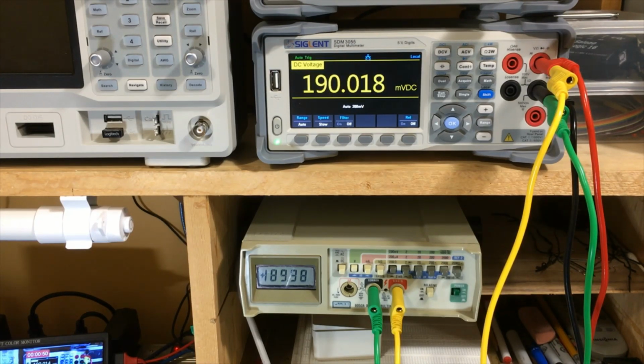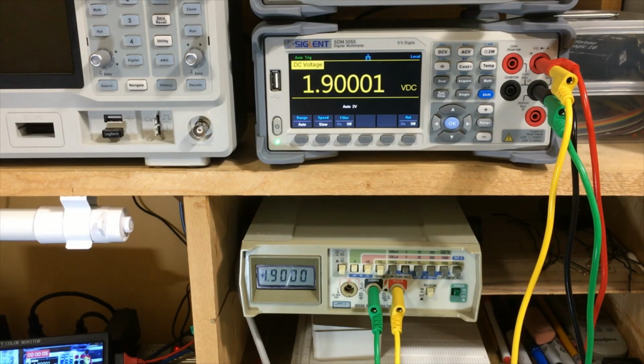We're going to do the 2-volt range. The Fluke recommend we check with 1.9000. So we are roughly there. Just that little bit. Yeah, so we got 1.9000. We have an extra digit on the Siglent, but that doesn't matter. And yeah, we're within 2 counts on the Fluke, so that's well within specification.